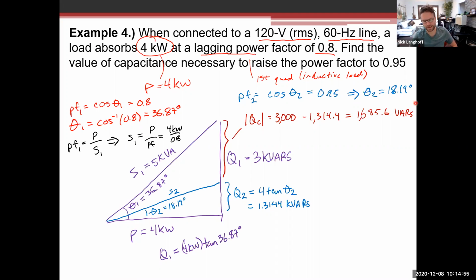Now we can calculate how much capacitance is needed. Realize Q2 is equal to Q1 plus the reactance from the capacitor. This is less than zero, a negative reactance, so it's going to reduce the amount of Q1, reducing the total reactance.